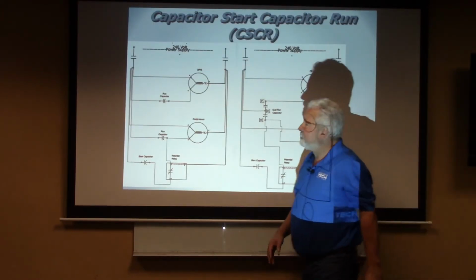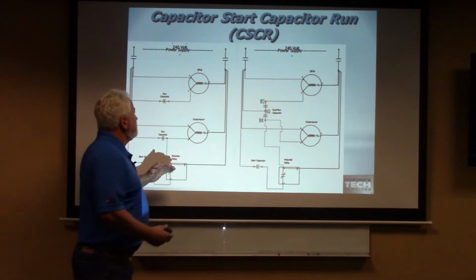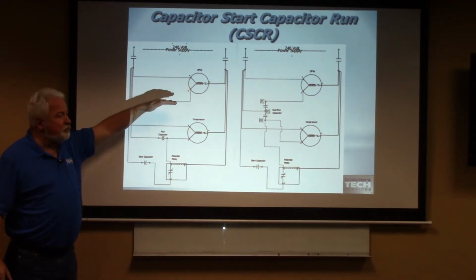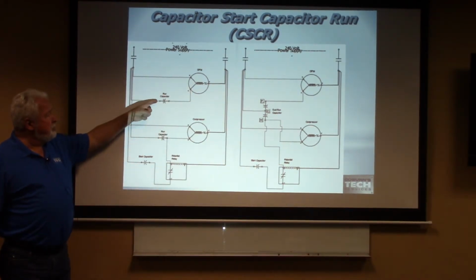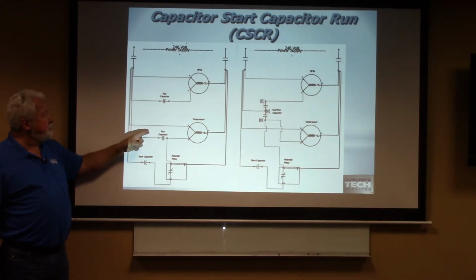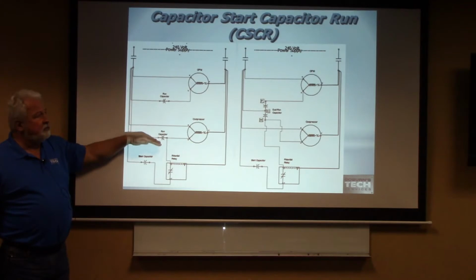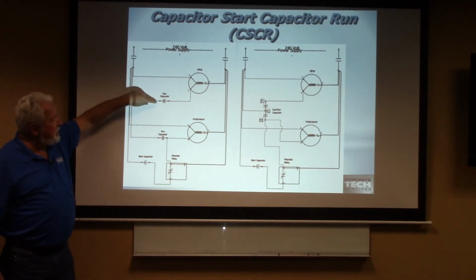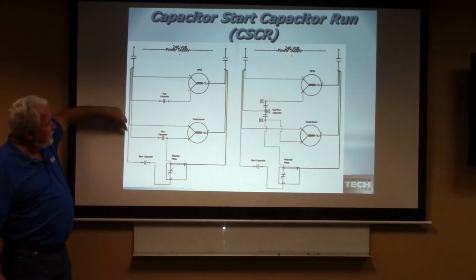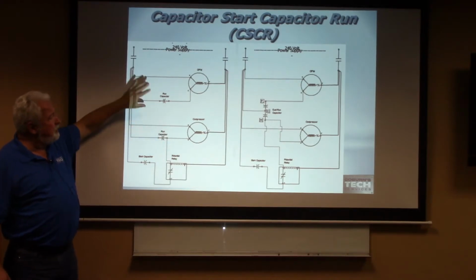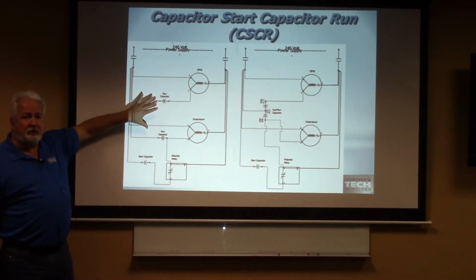All right. So here's a circuit with the outdoor fan motor and the compressor. And you'll notice your run capacitor in each of them. Two separate capacitors. Comes from the line through the capacitor to the start winding. Comes from the line through the capacitor to the start winding. That would be two separate capacitors.